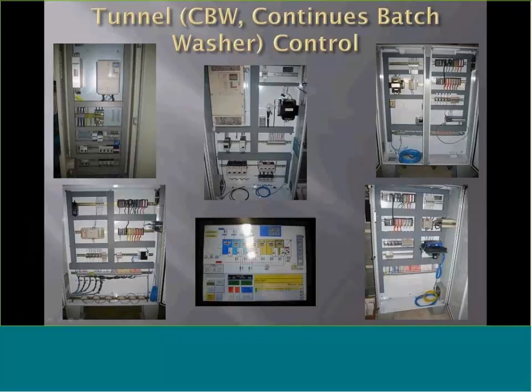One thing here I wanted to show you, how important this was: the bottom right-hand picture, that cabinet was sent down to Honduras, and at the time in Honduras there's no internet. The plant didn't have internet. There's no internet on the road or close by for the plant, and there again we needed monitoring. If you look right here, you see the cheap little router on top. In the middle of that black box is a BGAN satellite system. I researched and found a satellite system and mounted it in the control cabinet out on the floor.